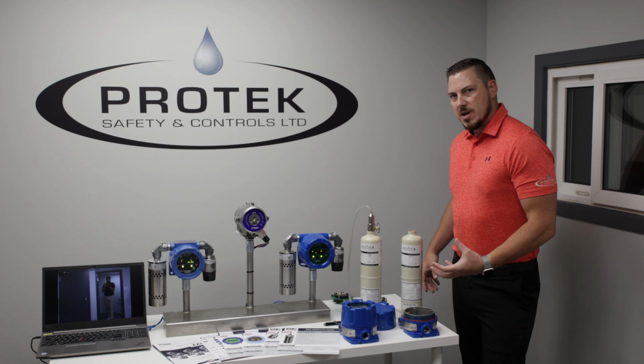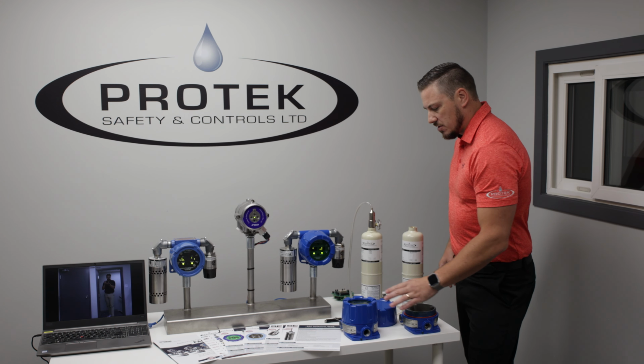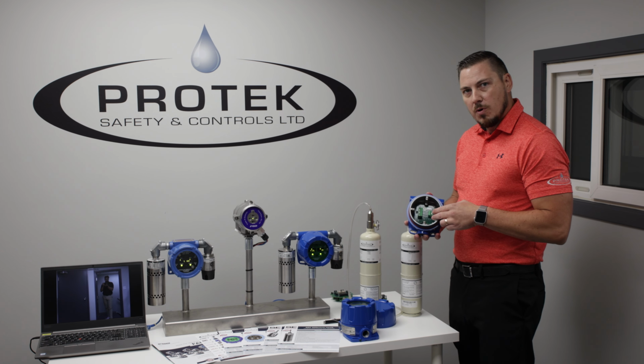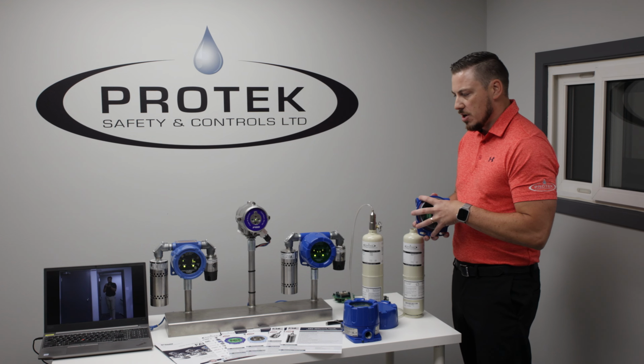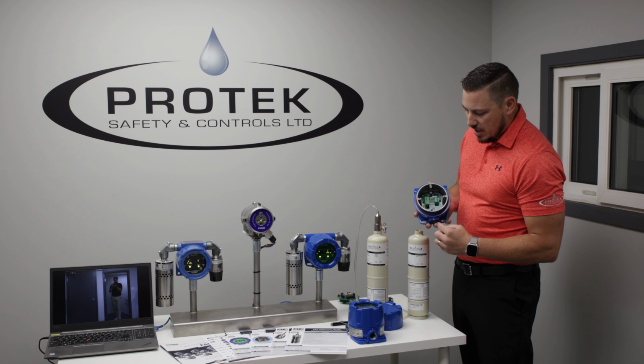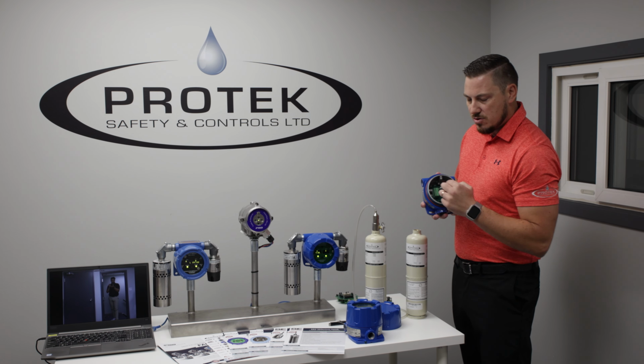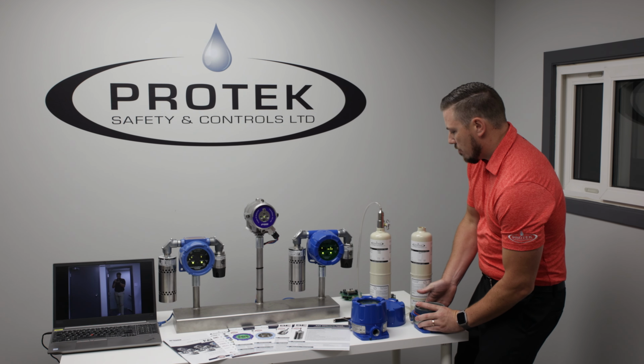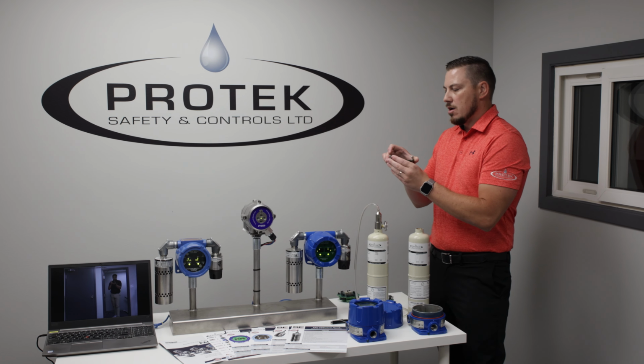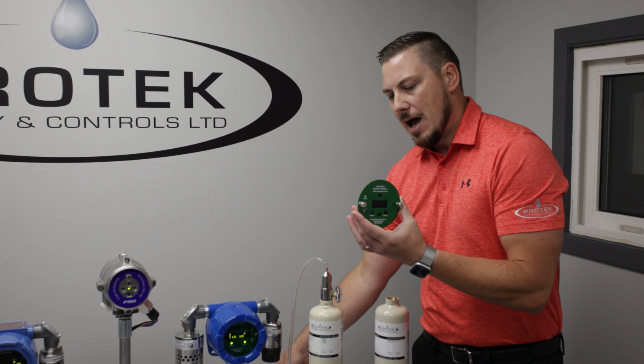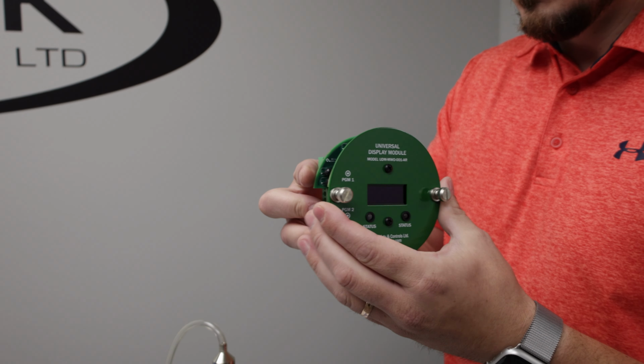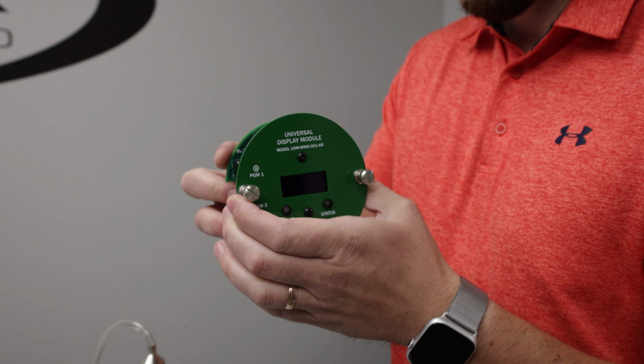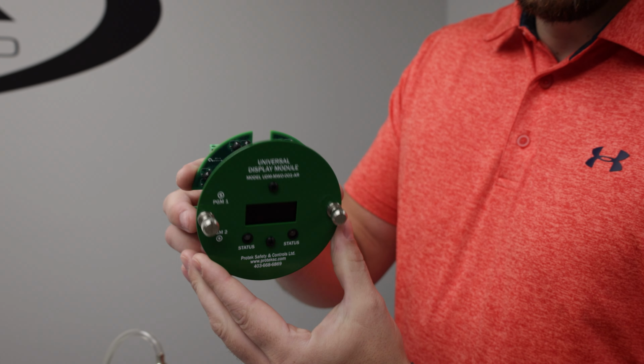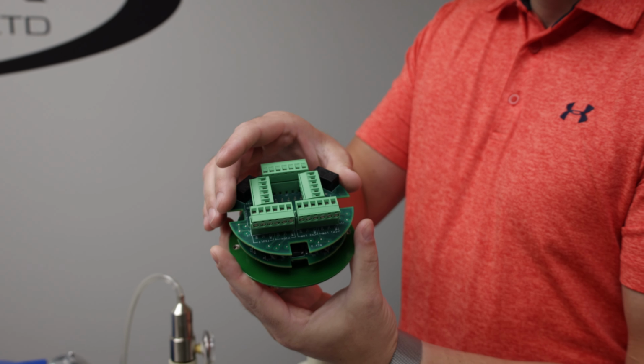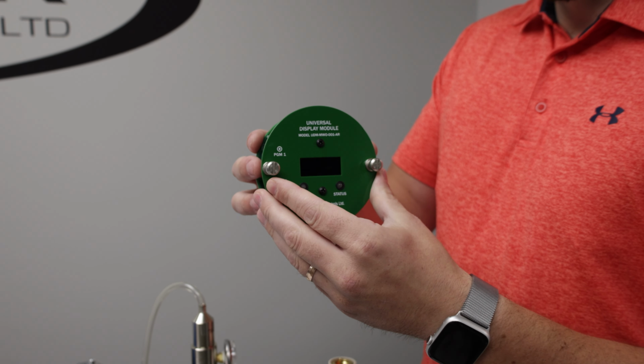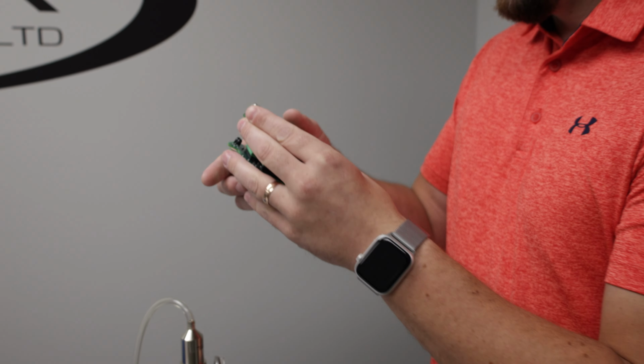I want to give you a little bit more information on the universal display module multi-wiring option. Not only do we take 2 or 3 wires in from the remote sensor separation back to your display module here, and connect our 4 wires from our sensor to our actual unit, but we also have the ability to add relay contacts to the back of the universal display module if needed, and they just snap on. Now we have relay contacts on the back, 4 contacts to be utilized as you see fit.